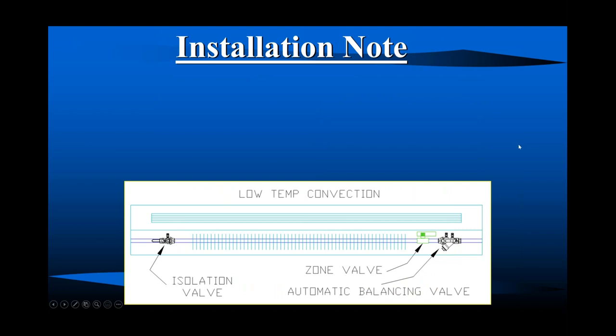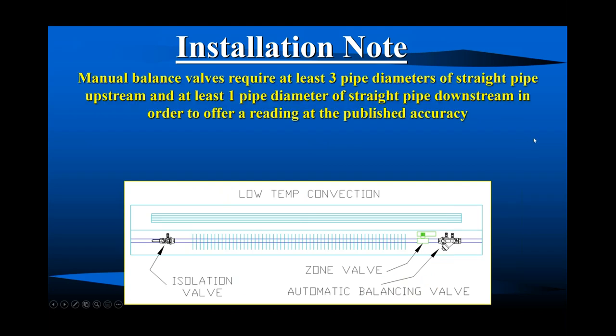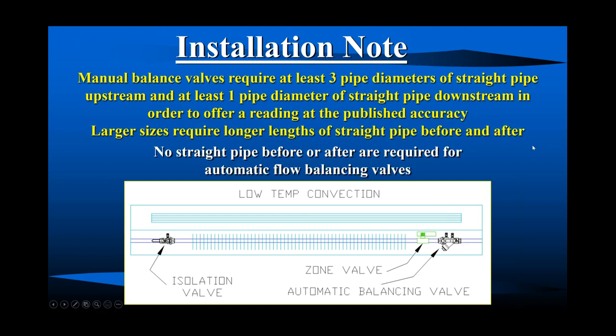Good question. So installation note, since it's a spring-loaded device, right? It's a cartridge, these types of valves, automatic flow balancing valves, don't require a straight pipe before or after. In all these new systems, you don't have a whole lot of room underneath the cabinetry of a convector, and much less a low temperature convector. So automatic flow balancing valves do not require straight pipe before or after. More often than not, that control valve is right next to the balancing valve. But in this case, if it's an automatic flow balancing valve, it doesn't affect the accuracy of it at all, compared to affecting the accuracy of a manual balance valve.